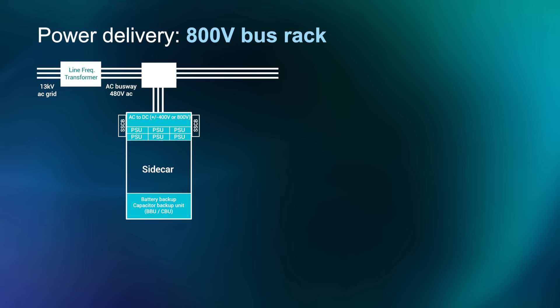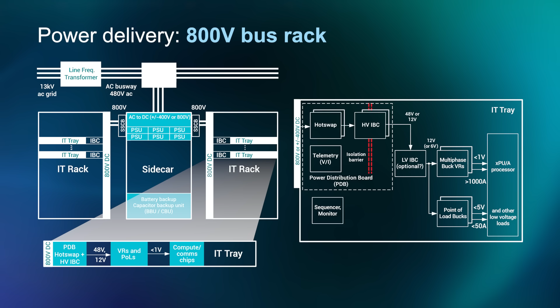In this architecture, we see 800 volts or plus or minus 400 volts DC coming out of the sidecar, and that's being distributed down the back of the IT rack. So this removes the need for any DC-DC power shelves in the IT rack. It does, though, introduce high voltage to the IT trays. This means that the power distribution board, or PDB, will need to be designed with high voltage in mind. The high voltage conversion ratio IBC will convert from 800 volts down to 48 volts or 12 volts, which means that there may be a low voltage IBC converting from 48 volts down to 12 or 6 volts, depending on the architecture. The key advantage of this approach is that it enables very high power delivered to the rack. Over 1 megawatt of power is now possible, and that improves the overall compute density.